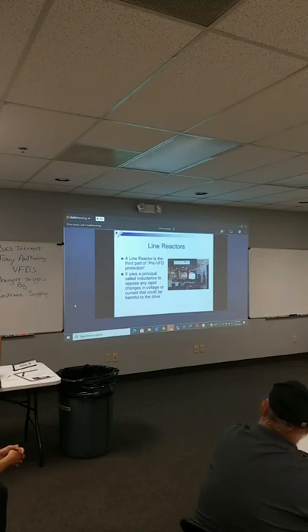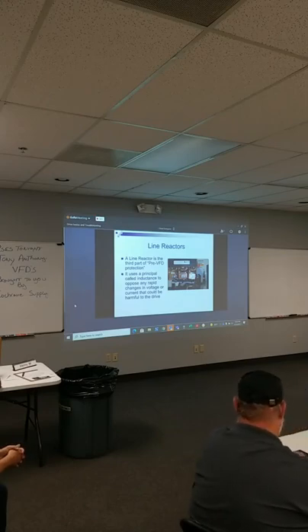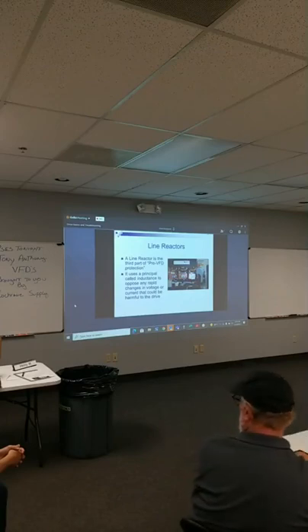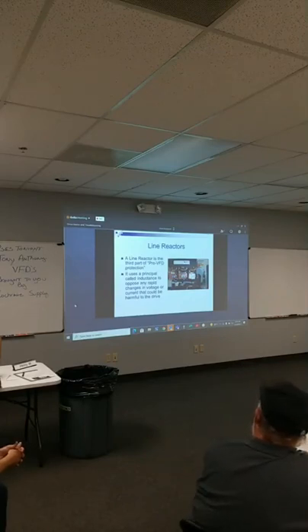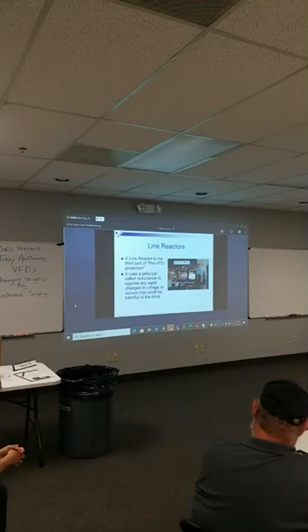What was happening was the distortion from that drive was just enough to put him over the top. Because all the other stuff he had done, like the lighting, and he had other drives in there, they got him close to where his transformer couldn't handle it. And we were the tipping point. So if you're going into a building that's already got a lot of drives, it's something to think about. Because you may be the tipping point. If you're the tipping point, it always then becomes your problem.